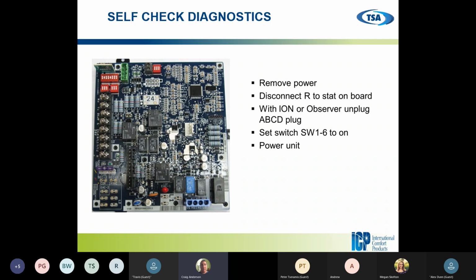So if you ever come down to changing your board, it's going to say right on the box, in a big orange sticker, don't forget to take the model plug out of the old board and put it in the new board. If you forget it, the furnace will not run in heating. You'll get an error code, and then you'll be starting a search for what's going on. So be mindful, when you're changing the board, that you're changing that little model plug up at the top.